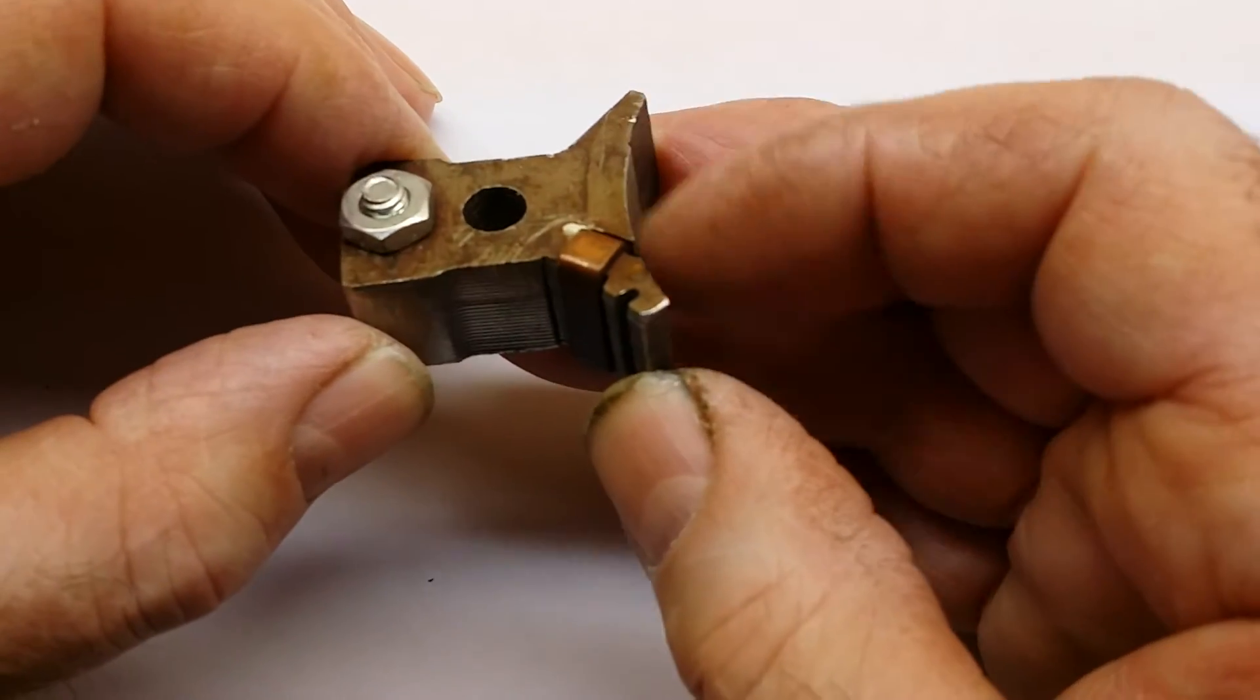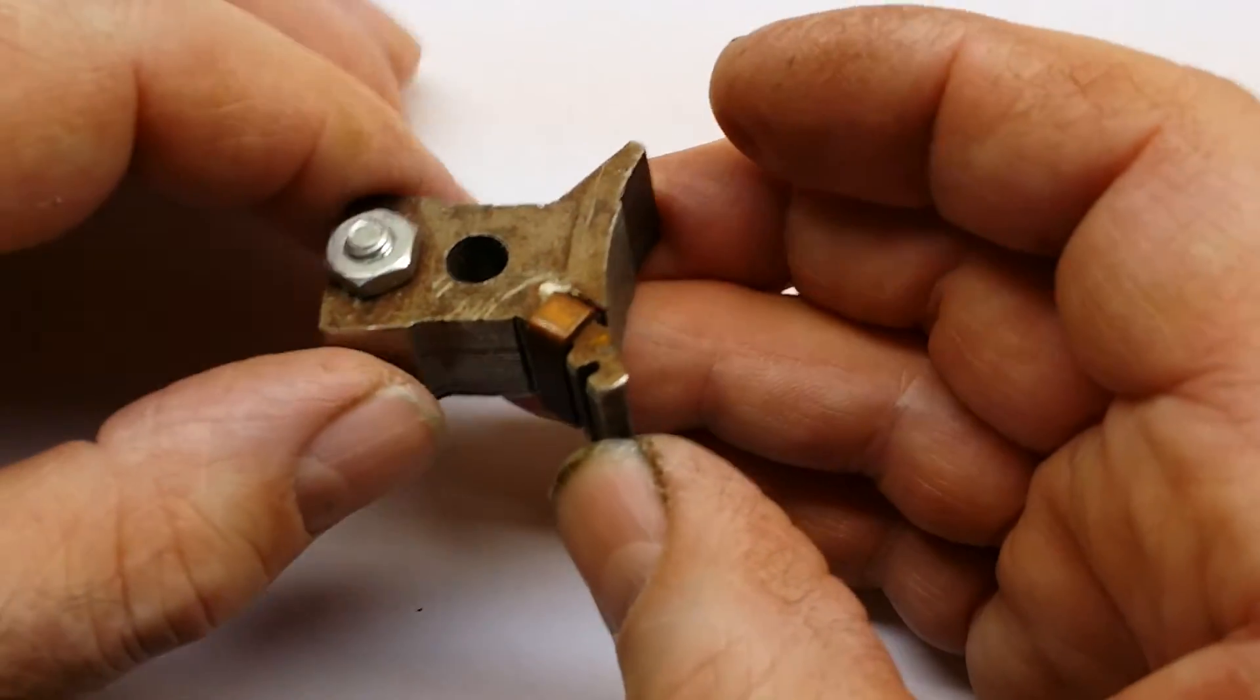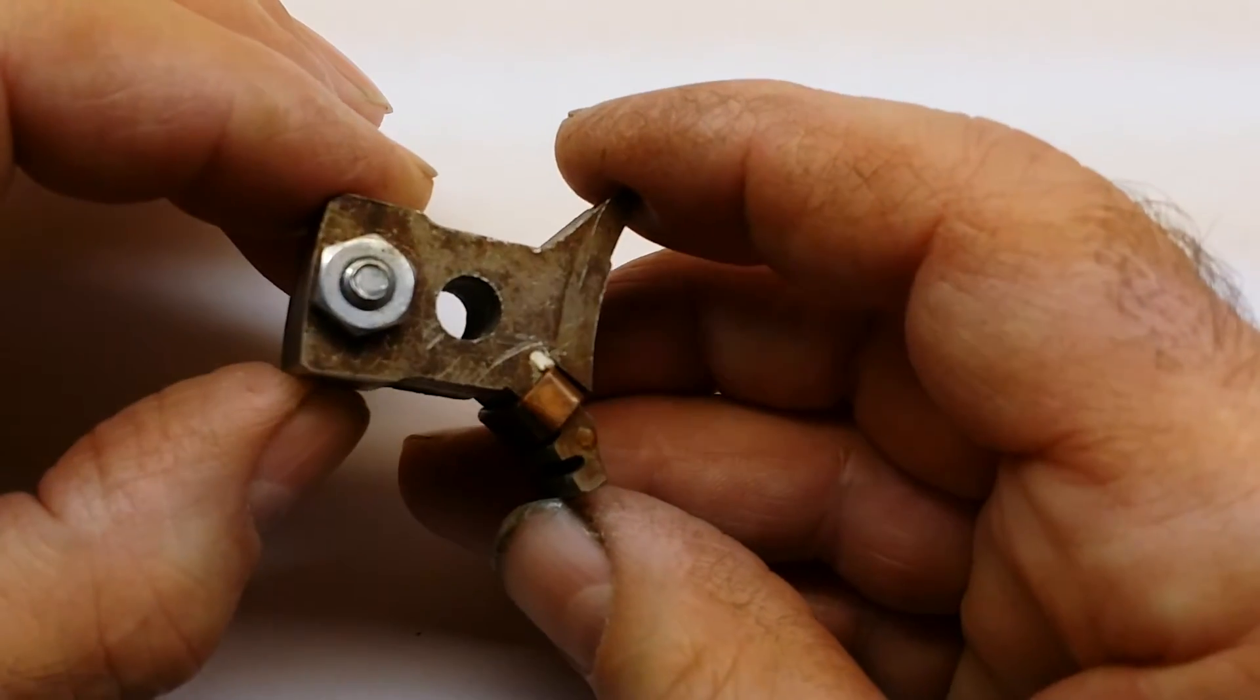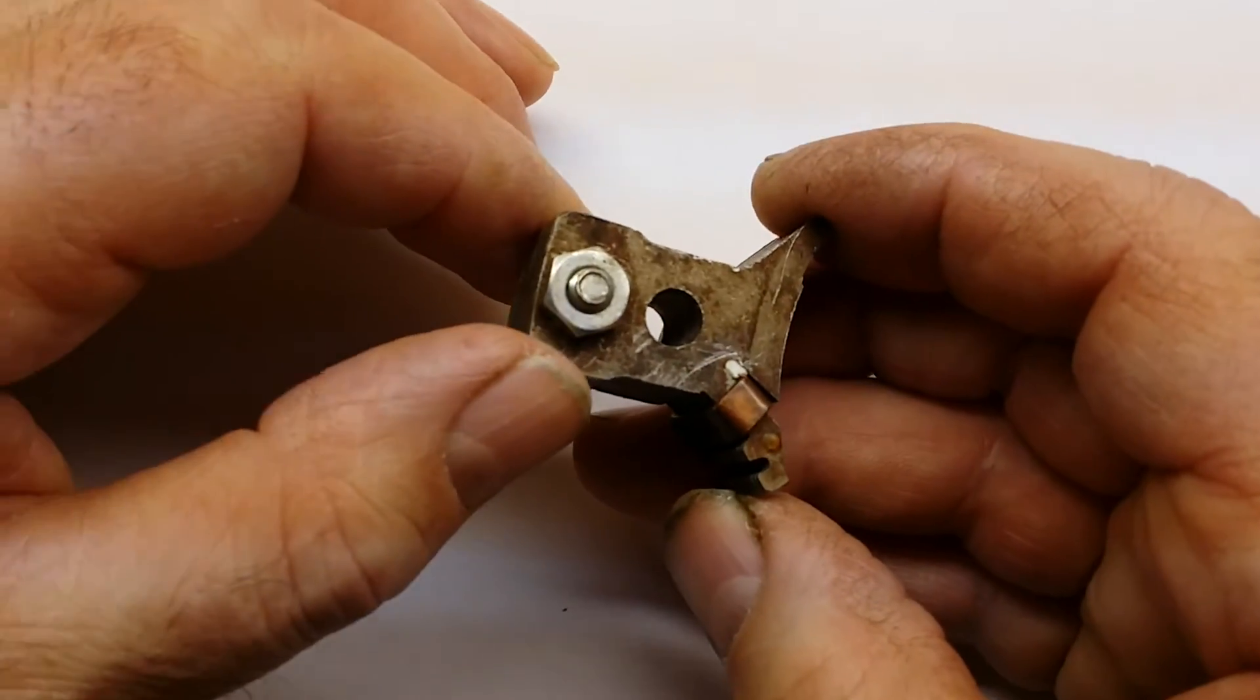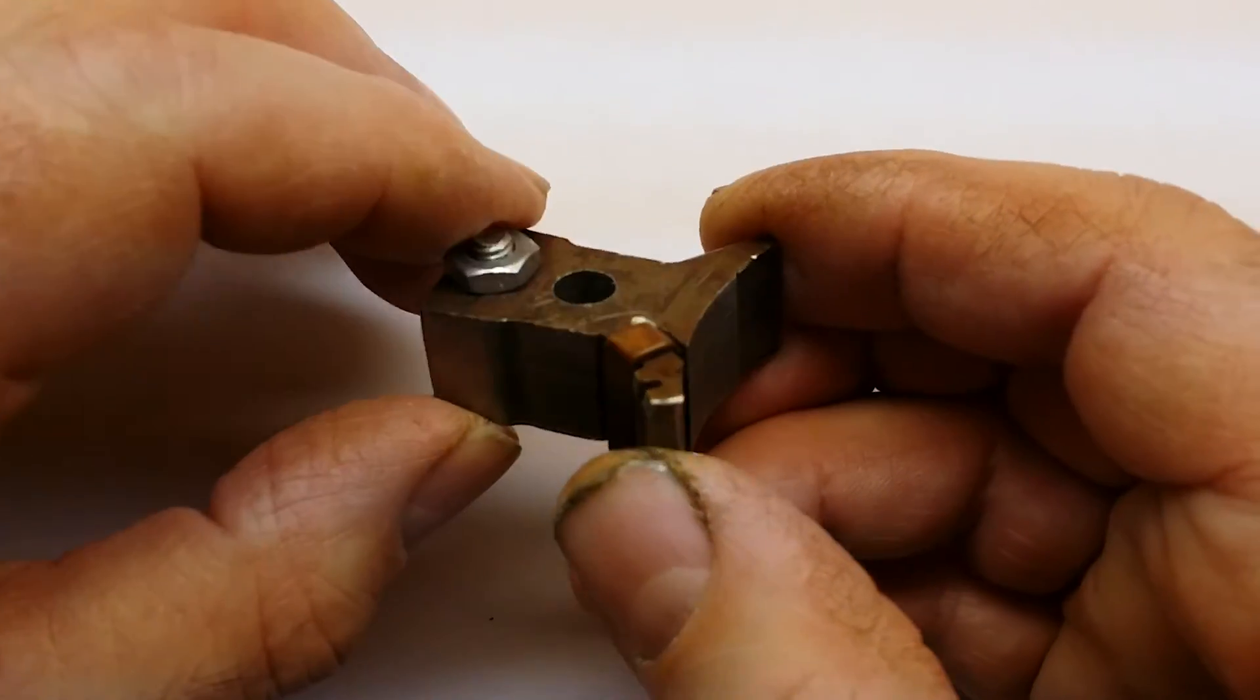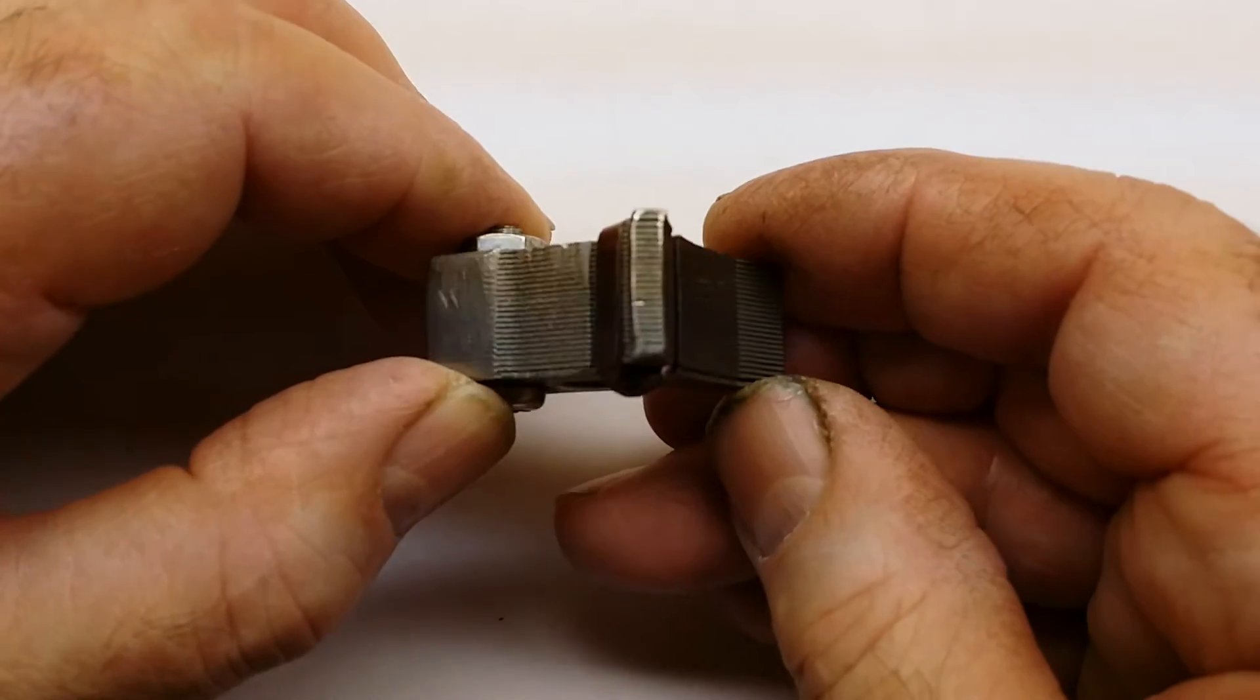The curved section is usually about five thousandths of an inch from the rotor, or about the thickness of a piece of paper. The reason for this closeness is for the best magnetic transfer efficiency. The further away it is from the motor will cause reduced magnetic flux effect.